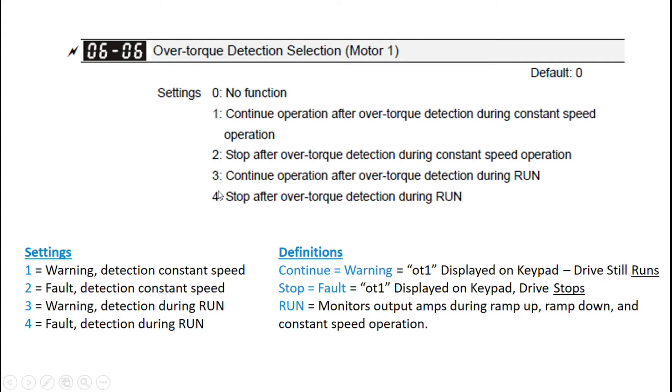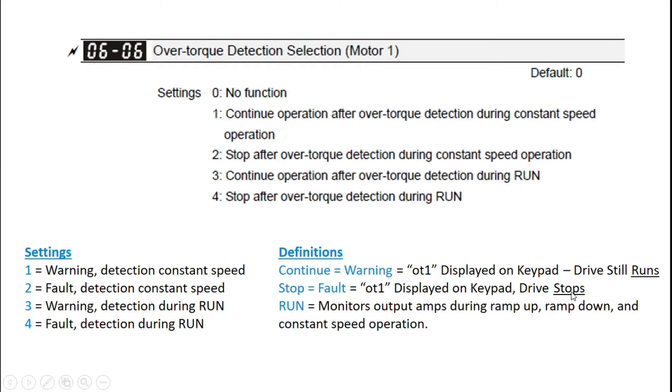Options two and four are both stop. So stop means the drive is going to actually have a fault. It's going to show the same OT1 on the display on the keypad, but the drive is going to stop and will need to be reset using the reset button on the keypad in order to run again.